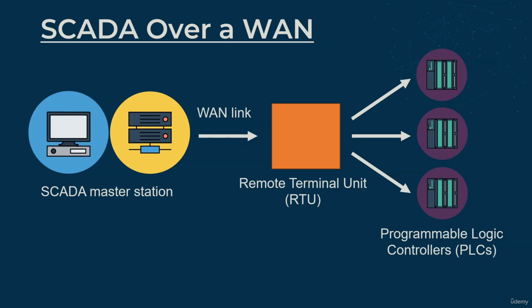Pictured on the screen, we have an example of what the general network flow would look like. On the left, we have our SCADA master station, which would have access to retrieve statistics from numerous PLCs. How many cars are we producing on the assembly line within one hour? Is everything working correctly? Do we have the right amount of pressure in this pipe? That kind of thing. Often, with SCADA, this happens over a wide area network, geographically dispersed. So we might have a WAN link from the SCADA master system that connects to what's called a remote terminal unit, RTU, which in turn allows access to the PLCs, the programmable logic controllers, in that remote location.